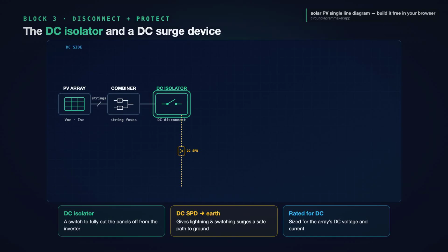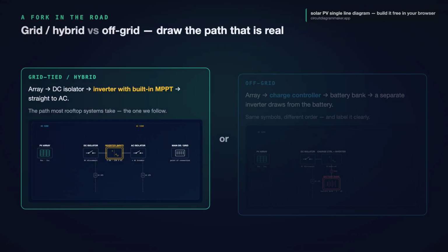Now, a fork in the road, because not every solar system is the same. If your system is grid-tied or hybrid, the DC line runs into an inverter with a built-in MPPT, maximum power point tracker, which squeezes the most out of the array and converts it straight to AC. That is the path most rooftop systems take, and it is the one we will follow.